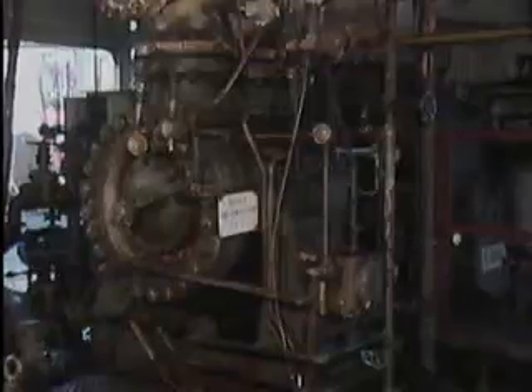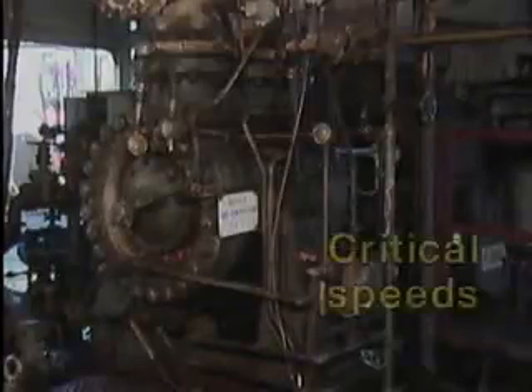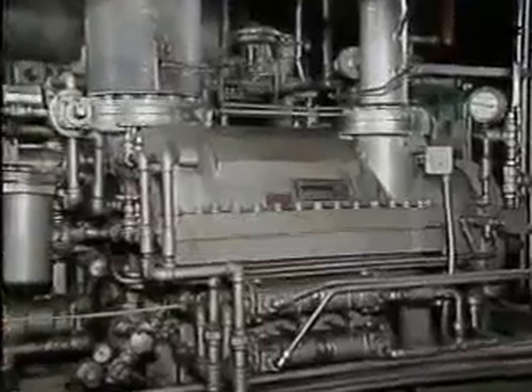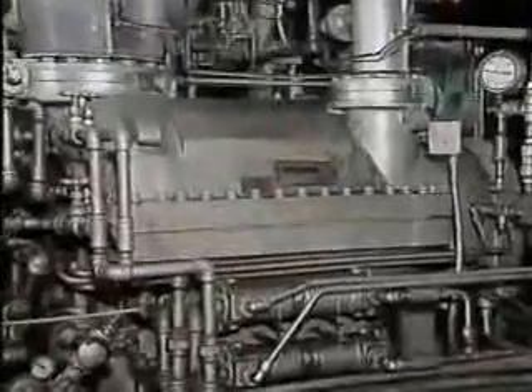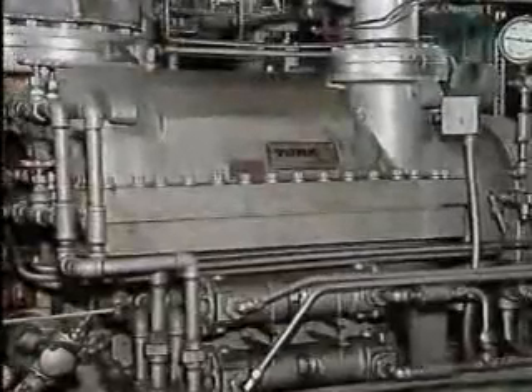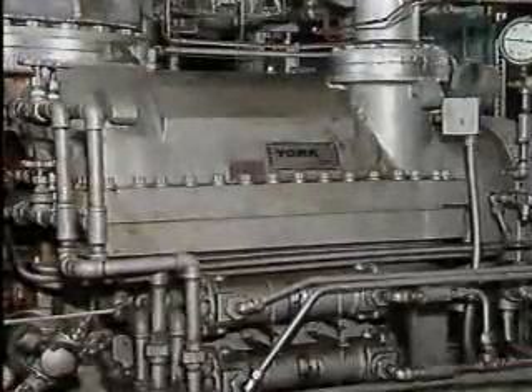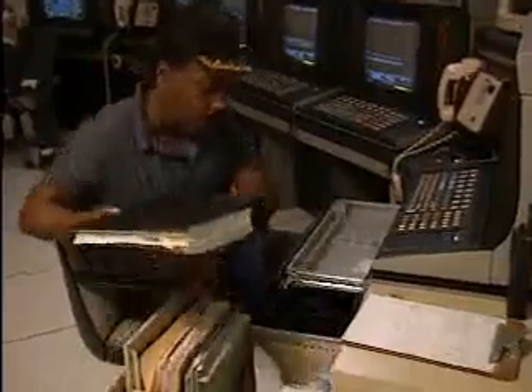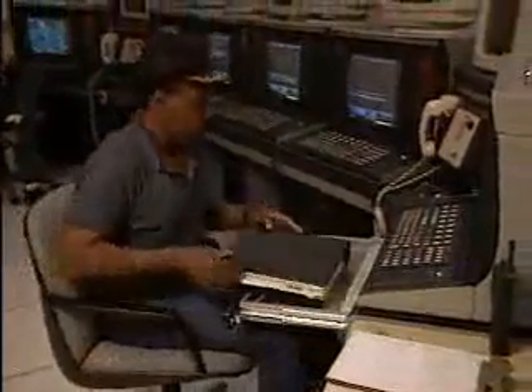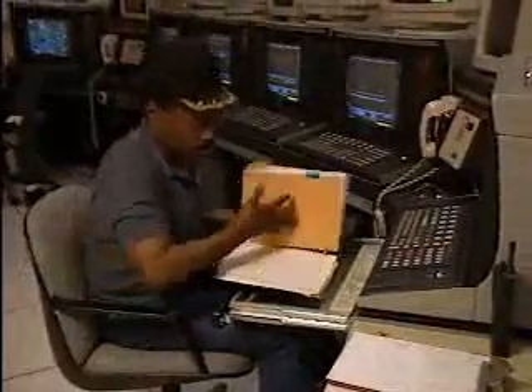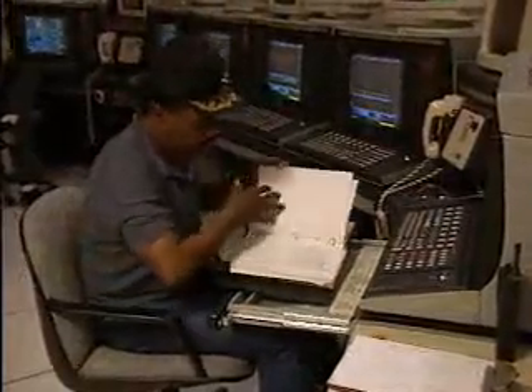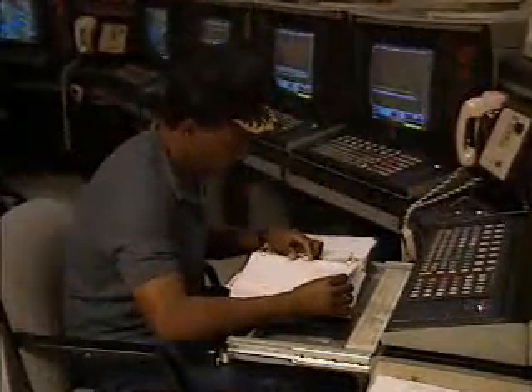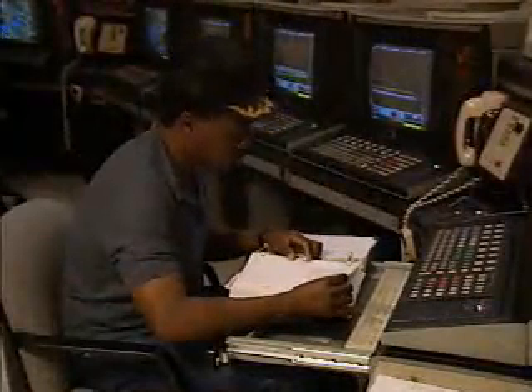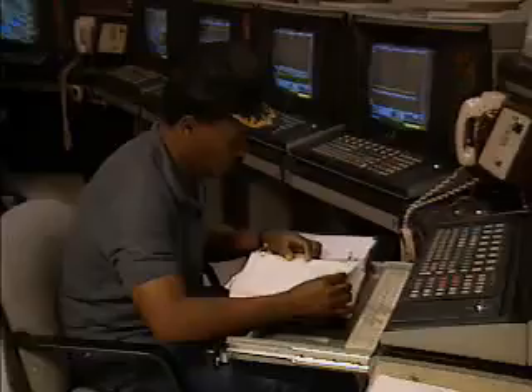However, in many centrifugal and axial compressors, certain rotational speeds, called critical speeds, cause severe vibration. This vibration is caused by the physical characteristics of the compressor's rotating parts. The vibration can be severe enough to seriously damage a compressor. Critical speeds are often identified in a compressor's operating procedures, and they occur when the compressor is at less than full operating speed. When a critical speed is reached, the ramp rate is usually increased to pass through the critical speed as quickly as possible.